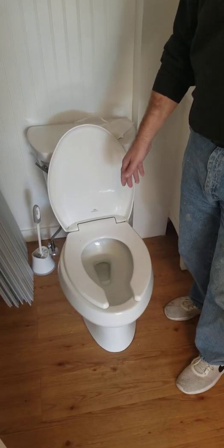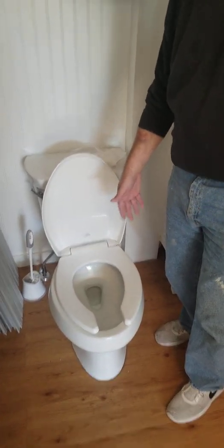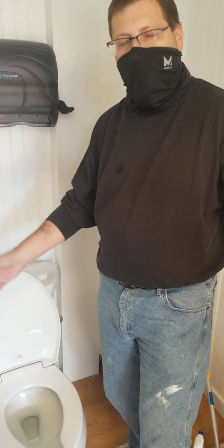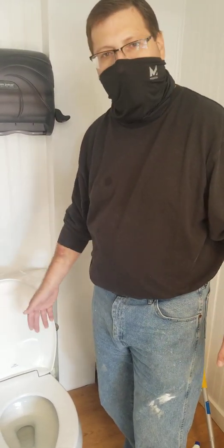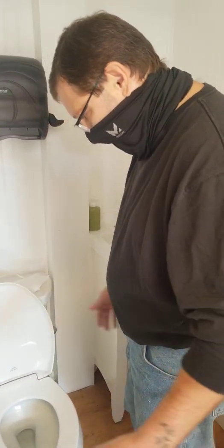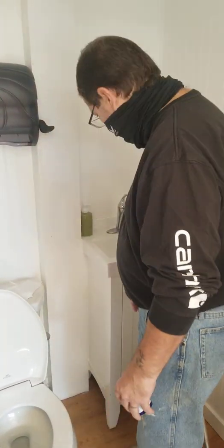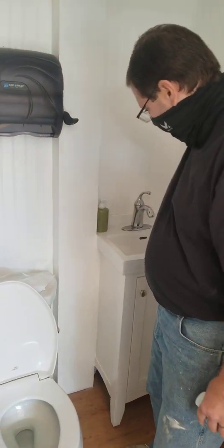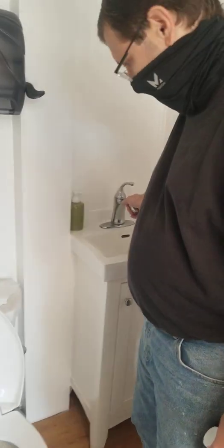All right, so we're in the left side, cellular side of the commercial building. We did the tab test here. We waited, and this toilet's fine. Speaking with the tenant as well, she has not heard anything, no filling on its own, nothing unusual happening. I don't see any blue coming through. It's been a while. The faucet is dry. There's no dripping in here. There is no indication of a leak in this bathroom.